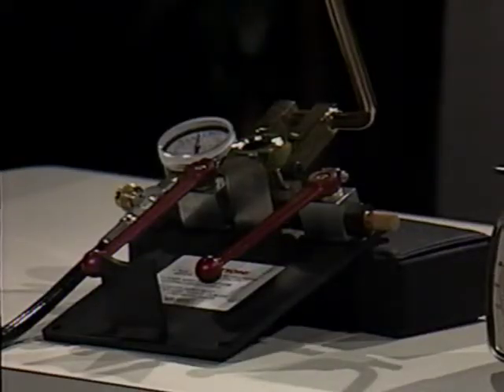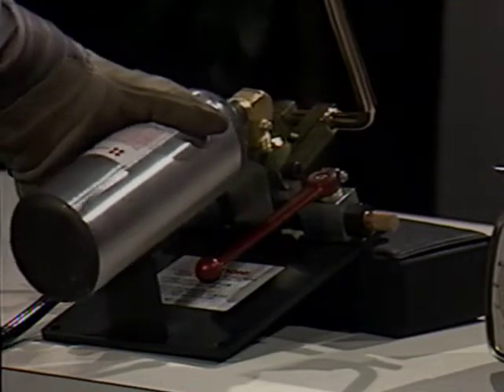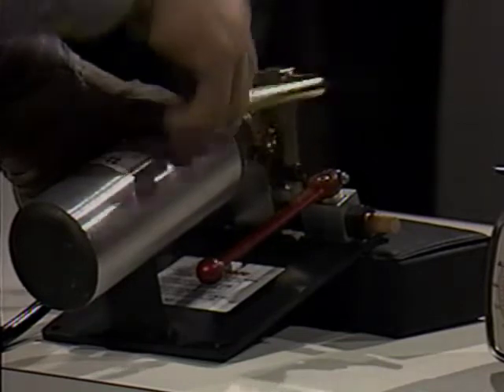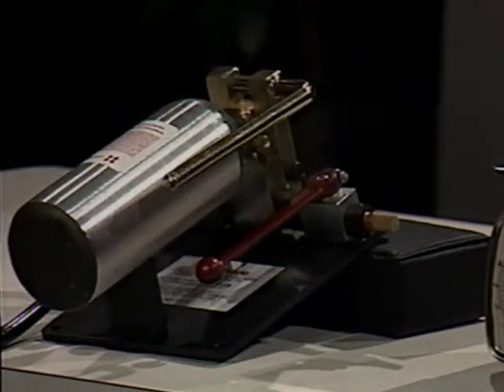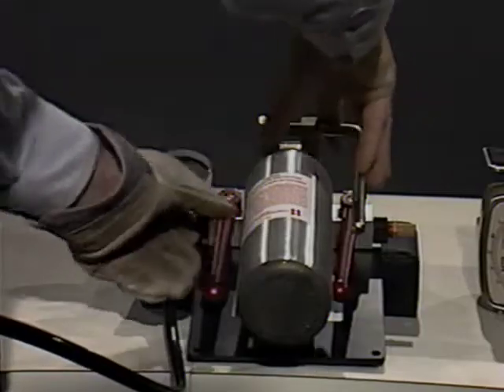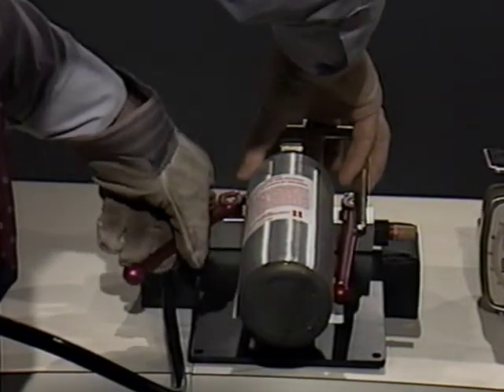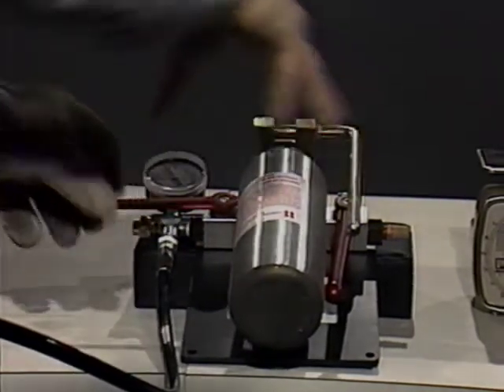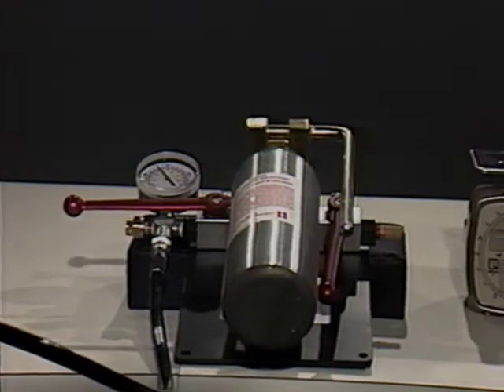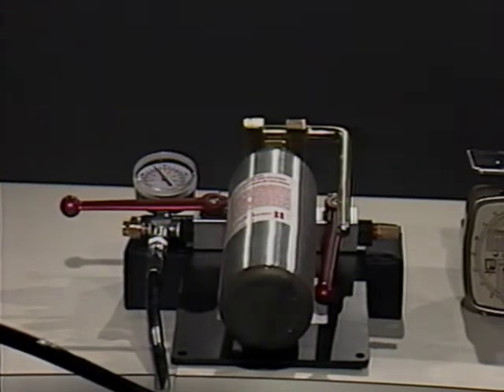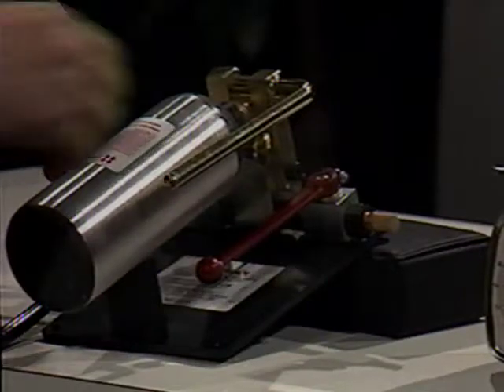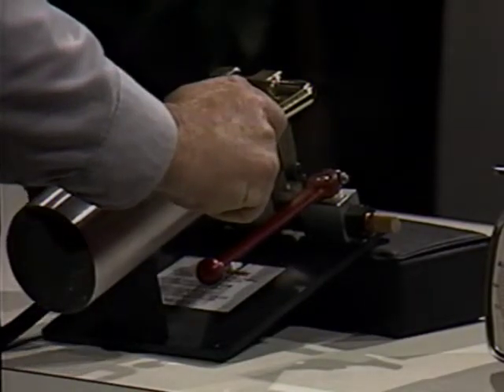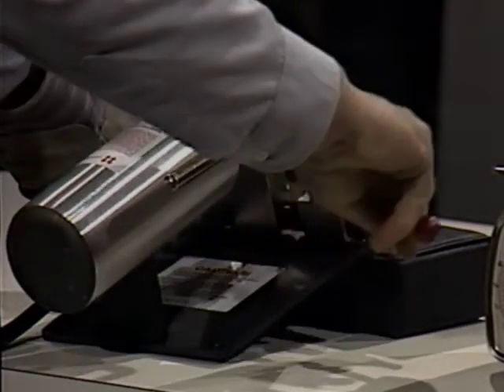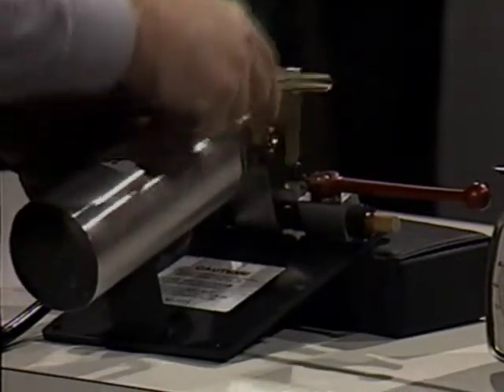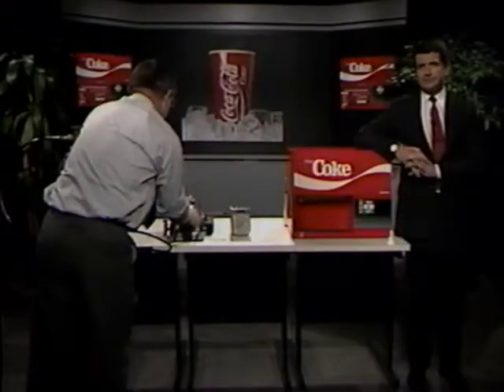Then place a 1 1/4 pound empty cylinder from the freezer into the filling head and close the latch. Open the fill valve at the fill head and allow the gas to flow into the cylinder for about 45 seconds or until the gas stops flowing. Shut off the fill valve and open the vent valve. Lift the latch and remove and weigh the cylinder.